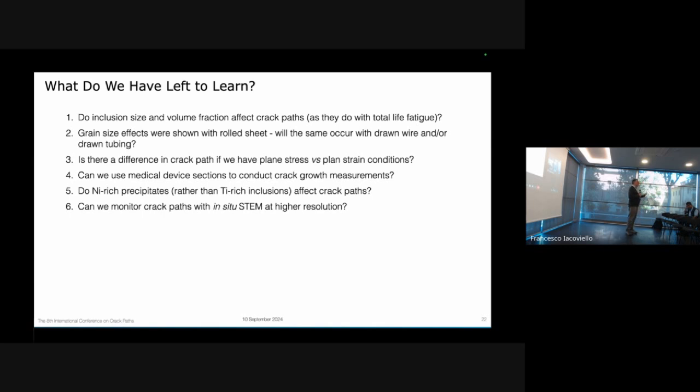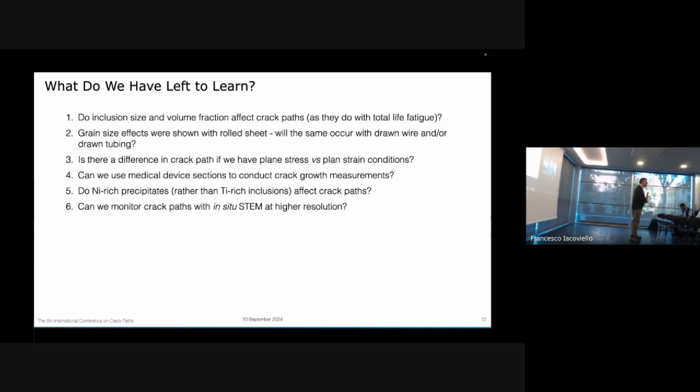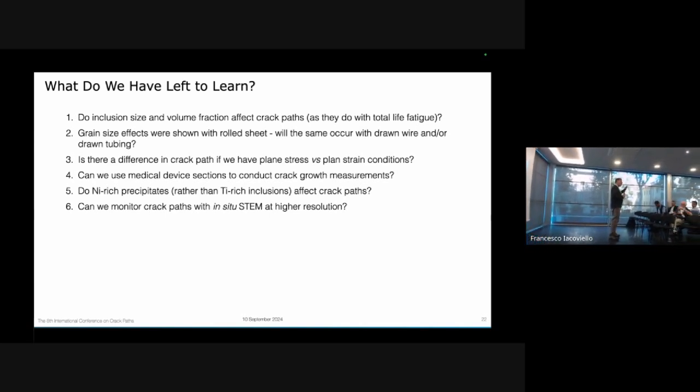Okay, look, delta K, for all the reasons you mentioned, doesn't really work with nitinol. Nitinol is too different from your normal linear elastic material. You know why we use it? Because there isn't anything out there. That's number one. Number two, what we're actually doing when we're doing these tests, whether on the benchtop or in theory, because we have some other models, is they're all proportional to the load, right? To the P. So we can say, it's not exactly correct, but it's getting us in the direction of the answer. It is not the answer.